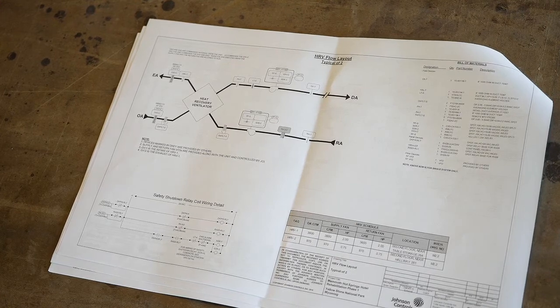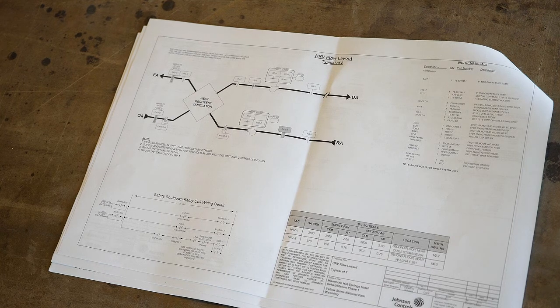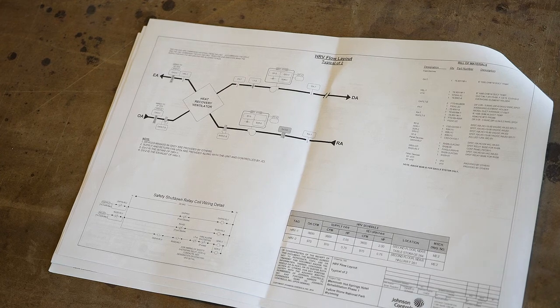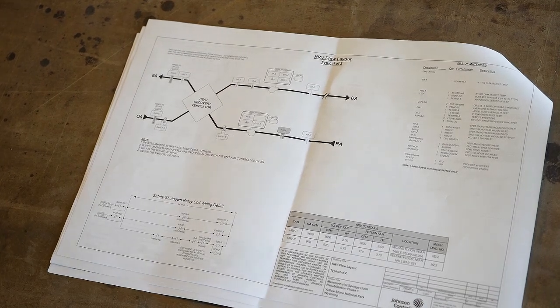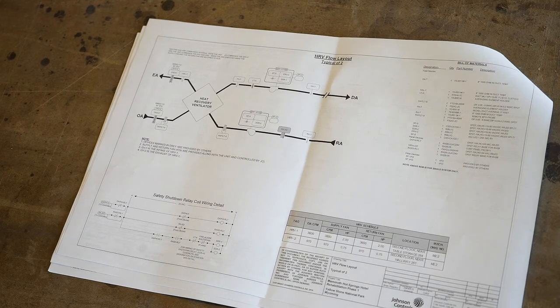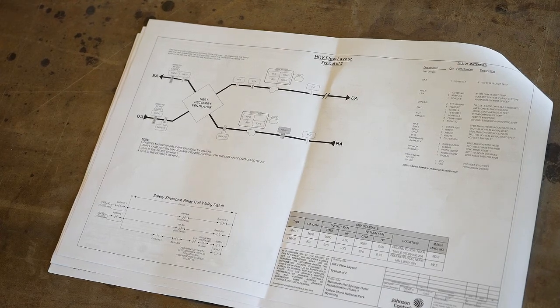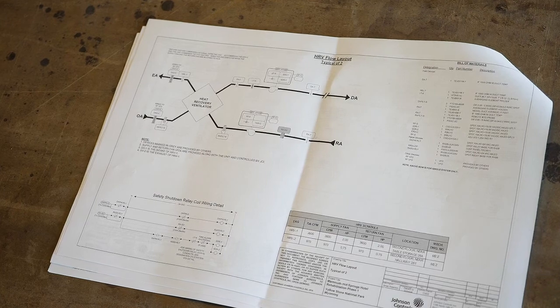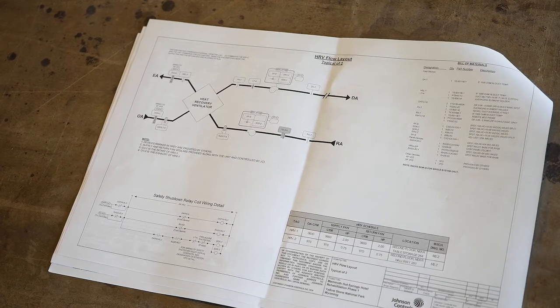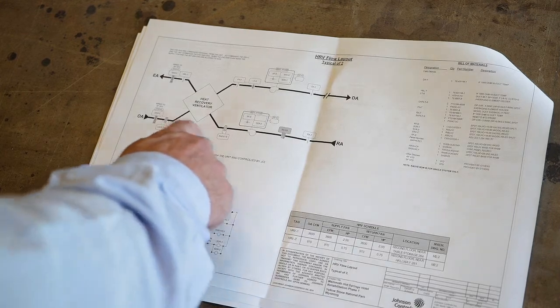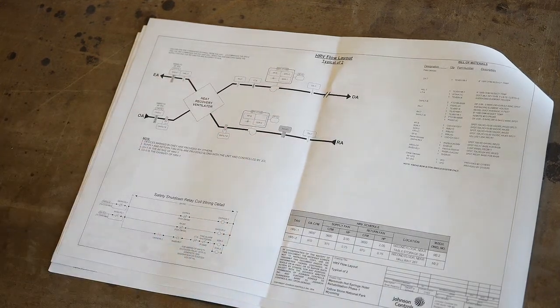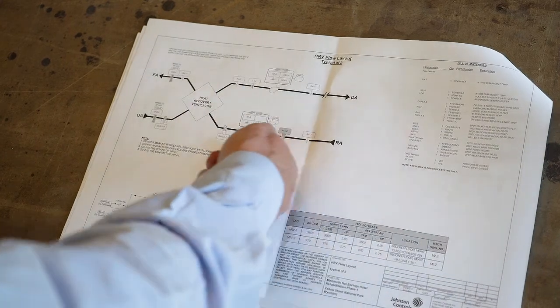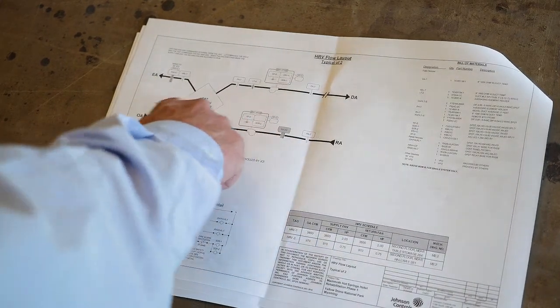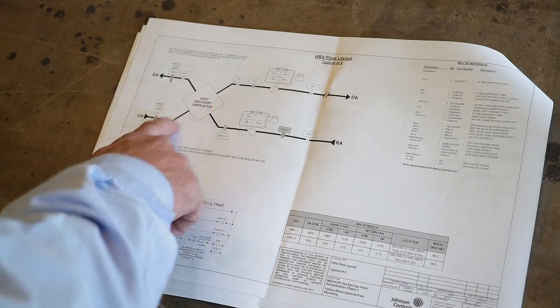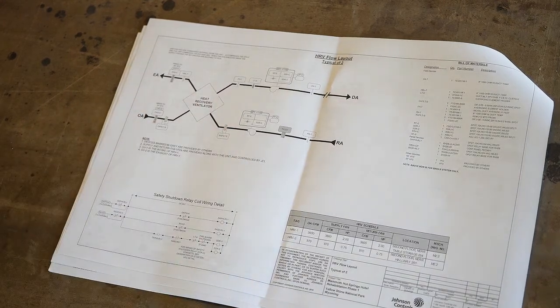Well, there were 4 on each inlet and exhaust. So 2 different sets. Yeah, 2 different sets. Those would be because we're going to filter the air we're dragging in from outside before we blow it into the room, and we're going to filter the air we're dragging out of the building before we run it through the heat exchanger. So the return air coming out of the building, you want to filter so you don't plug the heat exchanger, and the outside air coming in is filtered so you don't plug it with cotton or whatever.